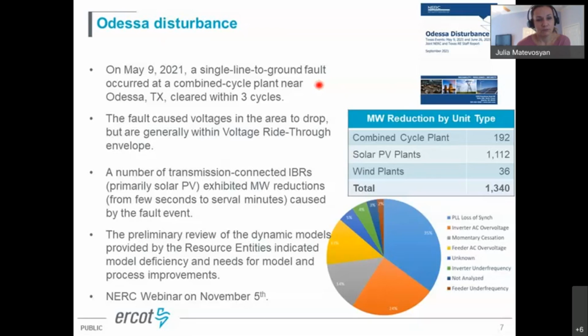The preliminary review showed that dynamic models provided by resource entities were not able to reflect all of the tripping issues that actually happened, and we need a process for model improvement. On the right-hand side in this pie chart, you can see percentages of different types of trip causes that happened, and the amount of generation we lost. This is what was lost in the initial event, just clearing the fault, and that was 192 megawatt of combined cycle plant. But cumulative solar plant loss was more than 1 gigawatt. What this is saying is that we are constantly improving the process of provision of models, model testing, model validation, but there are still some things that are not being caught in this process, and we still need to improve that going forward.